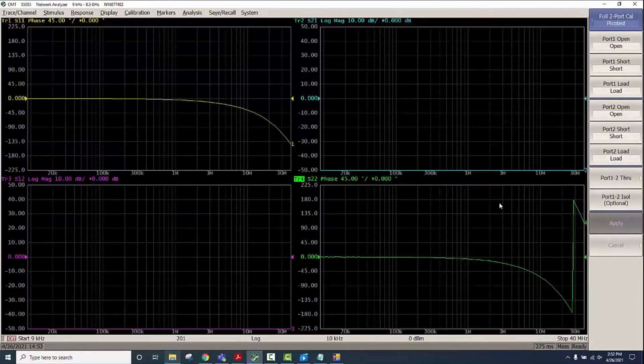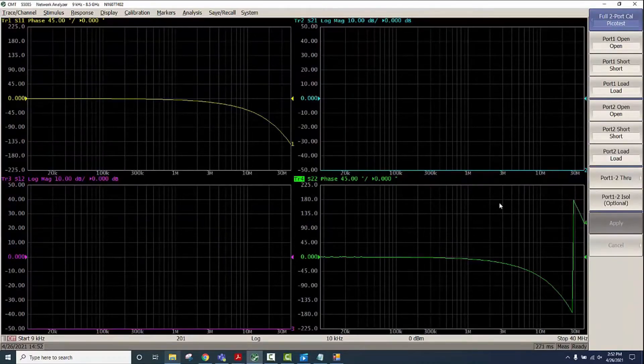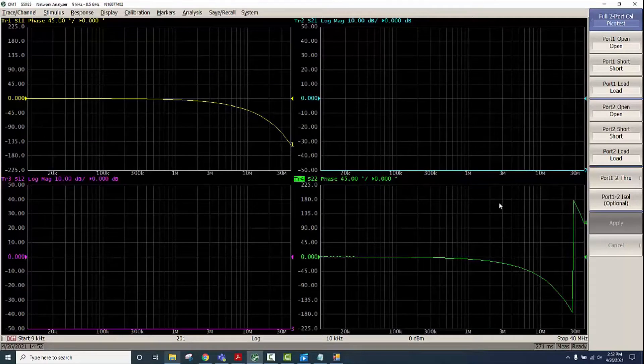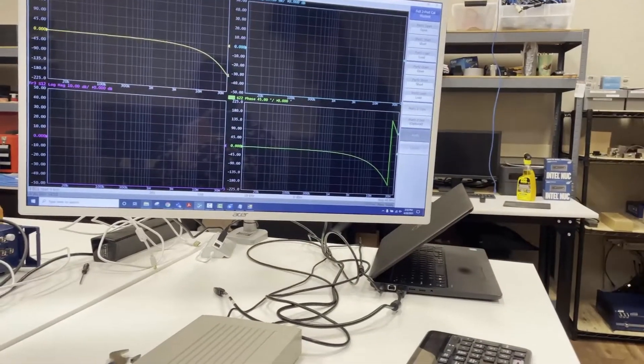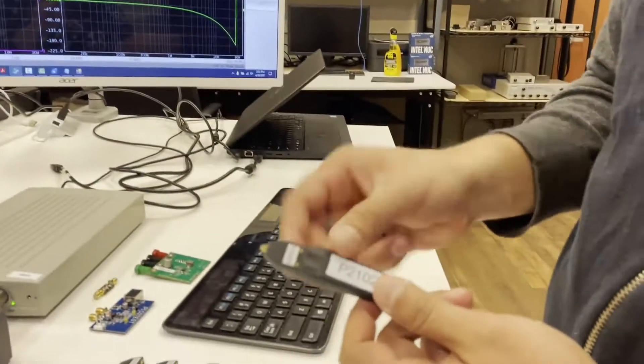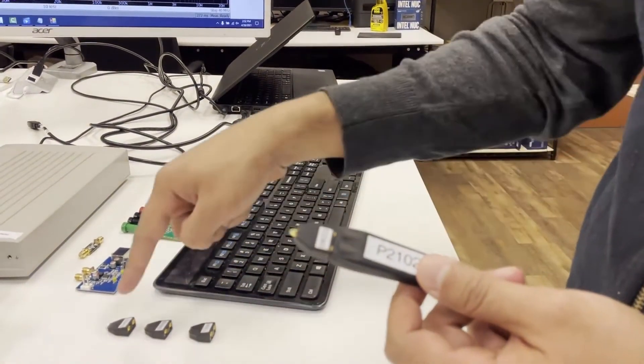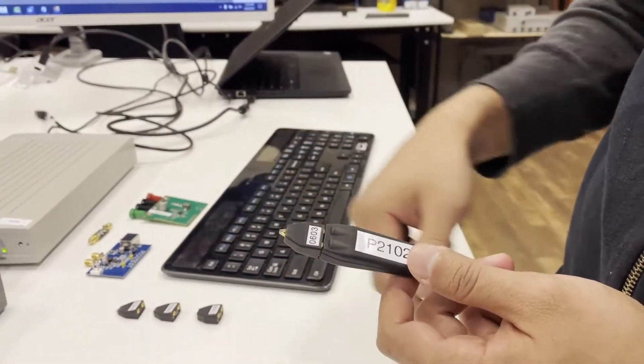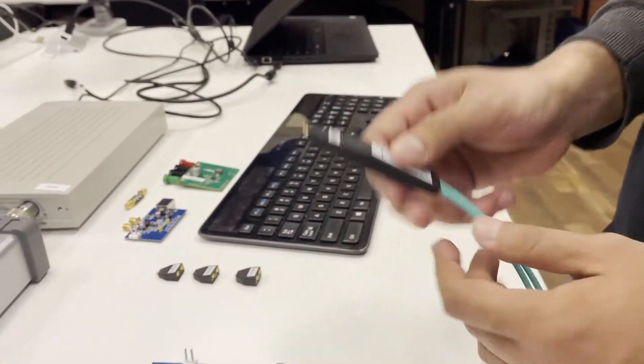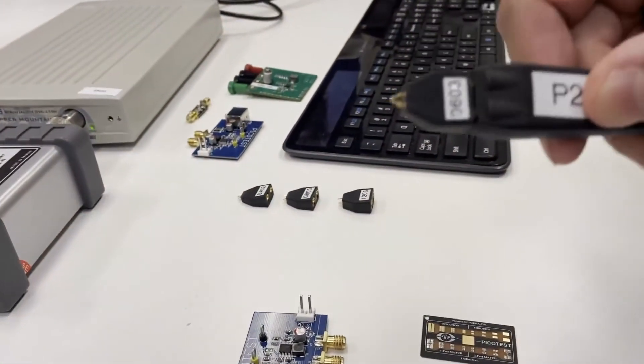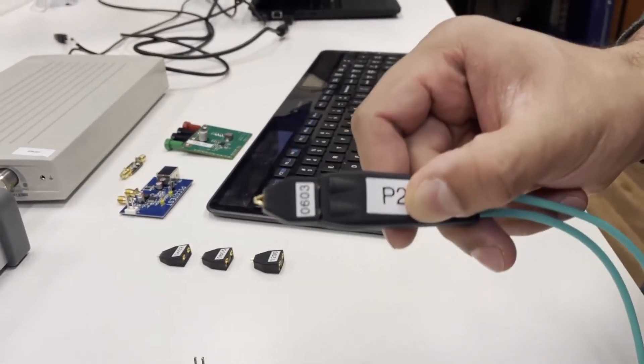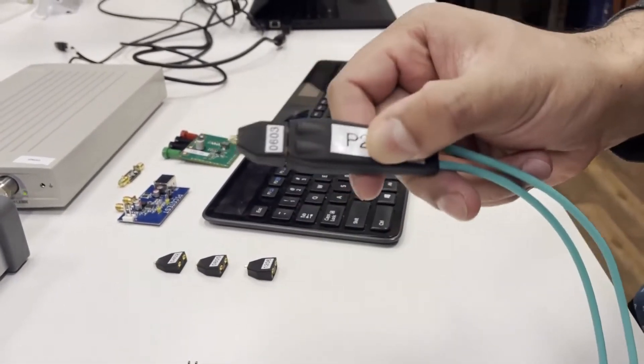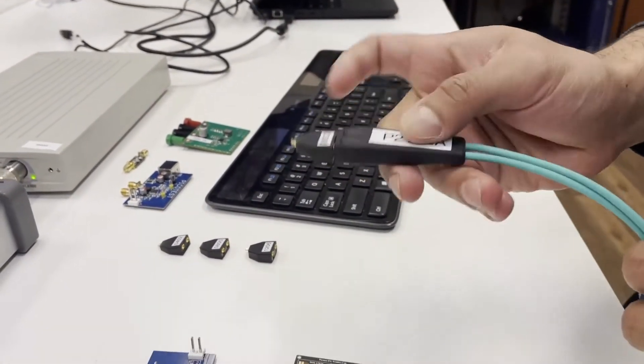Full two-port calibration. We will select the probe along with the tip. We'll use the 0603 but there are other tips to choose from as well. We'll be using the same tip to perform measurements so that's why we're using this for calibration.